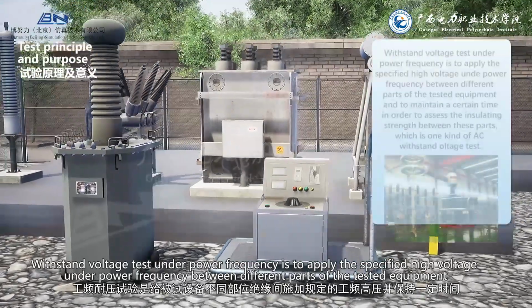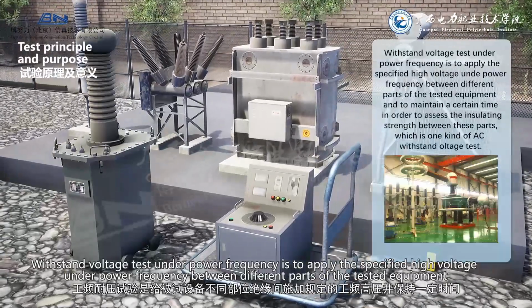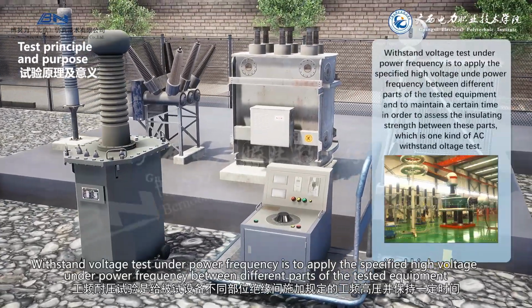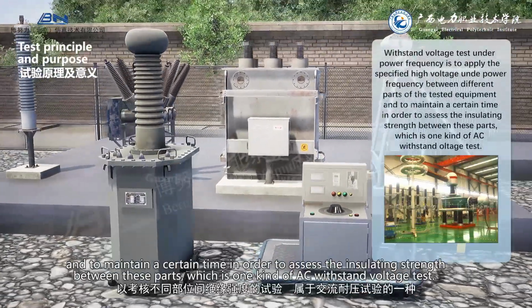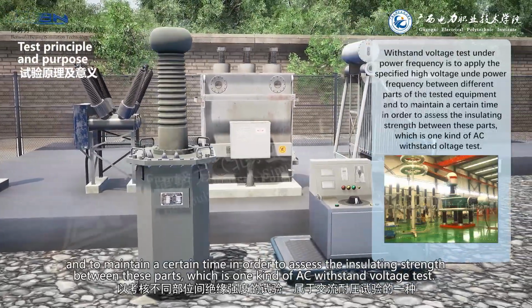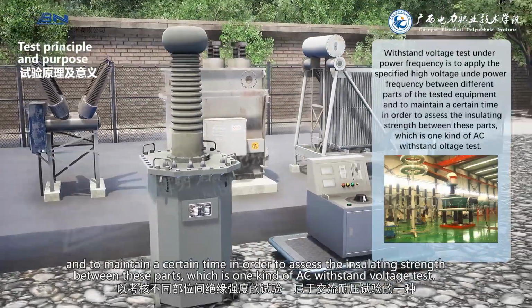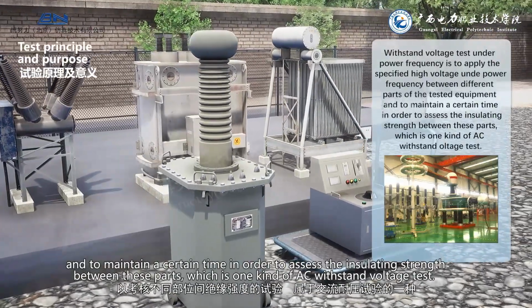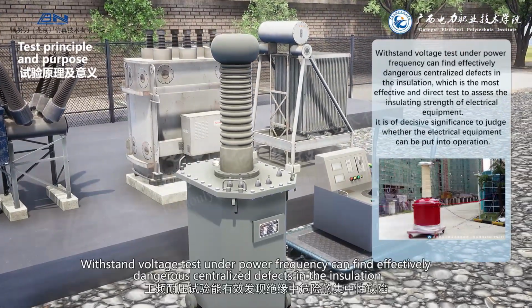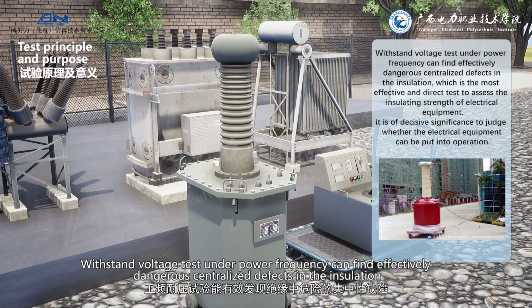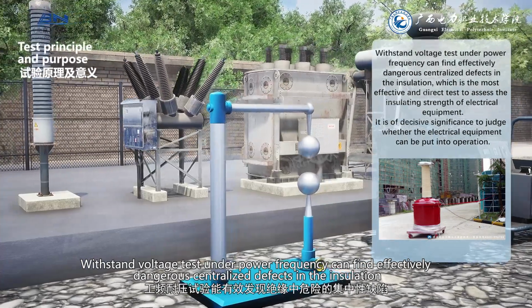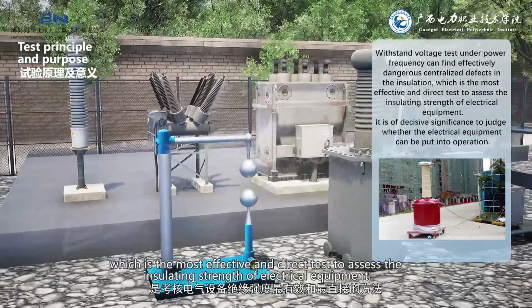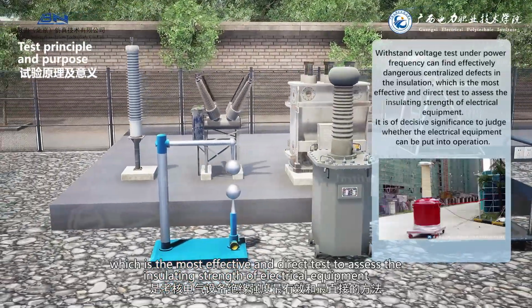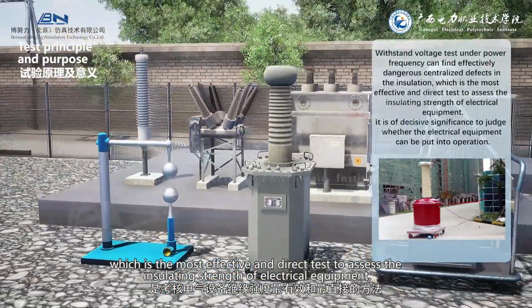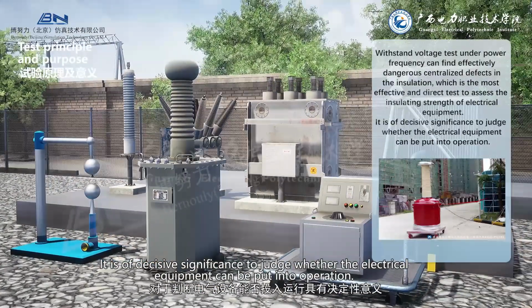Withstand voltage test under power frequency is to apply the specified high voltage under power frequency between different parts of the tested equipment and to maintain it for a certain time in order to assess the insulating strength between these parts, which is one kind of AC withstand voltage test. Withstand voltage test under power frequency can effectively find dangerous centralized defects in the insulation, and it is the most effective and direct test to assess the insulating strength of electrical equipment. It is of decisive significance to judge whether the electrical equipment can be put into operation.